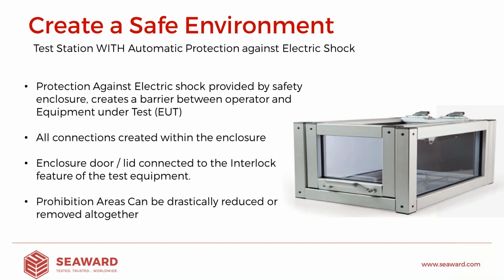The other main advantage for creating a test area with automatic protection, i.e. inside an enclosure, is that we can drastically reduce or remove altogether any prohibition zones that exist around the test area. They can certainly become much, much smaller because the risk of an outsider receiving an electric shock becomes exactly the same as the risk of the operator, which is effectively none. The product is being tested safely away inside a box. So therefore, the consideration in terms of how much space we have to give, how much reach space we have to move between the point of test and the workways can be much, much smaller, because the simple fact is we physically cannot come into contact with the product under test.